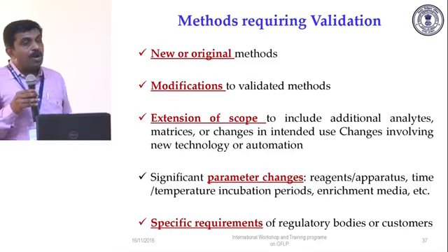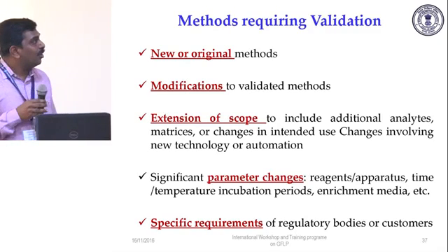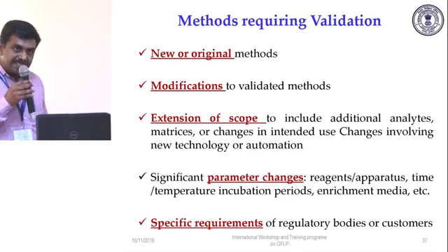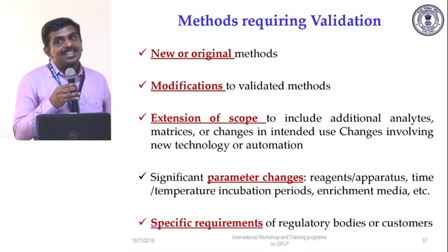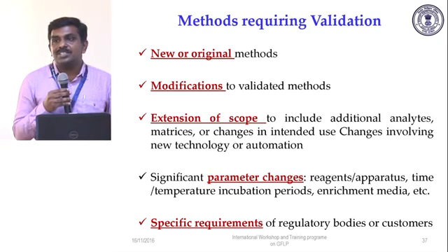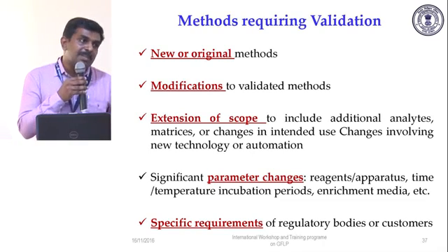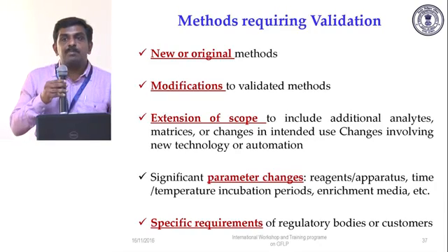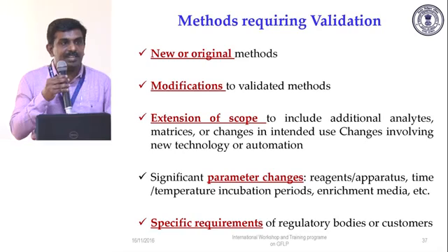See, methods requiring validation: new or original methods. Modifications to an existing validated method means you have validated but you have made a modification. Now, what is the modification? That is a critical thing. If you change a method, it calls for a validation. If you have made major changes in your equipment, it also calls for a validation.